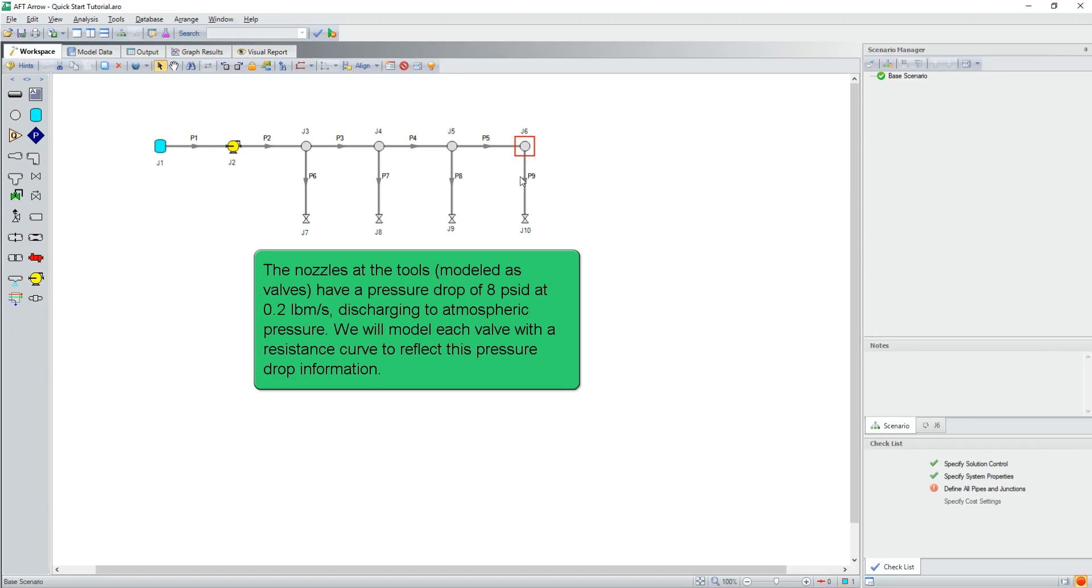The nozzles at the tools, modeled as valves, have a pressure drop of 8 PSID at 0.2 pound mass per second, discharging to atmospheric pressure. We will model each valve with a resistance curve to reflect this pressure drop information.